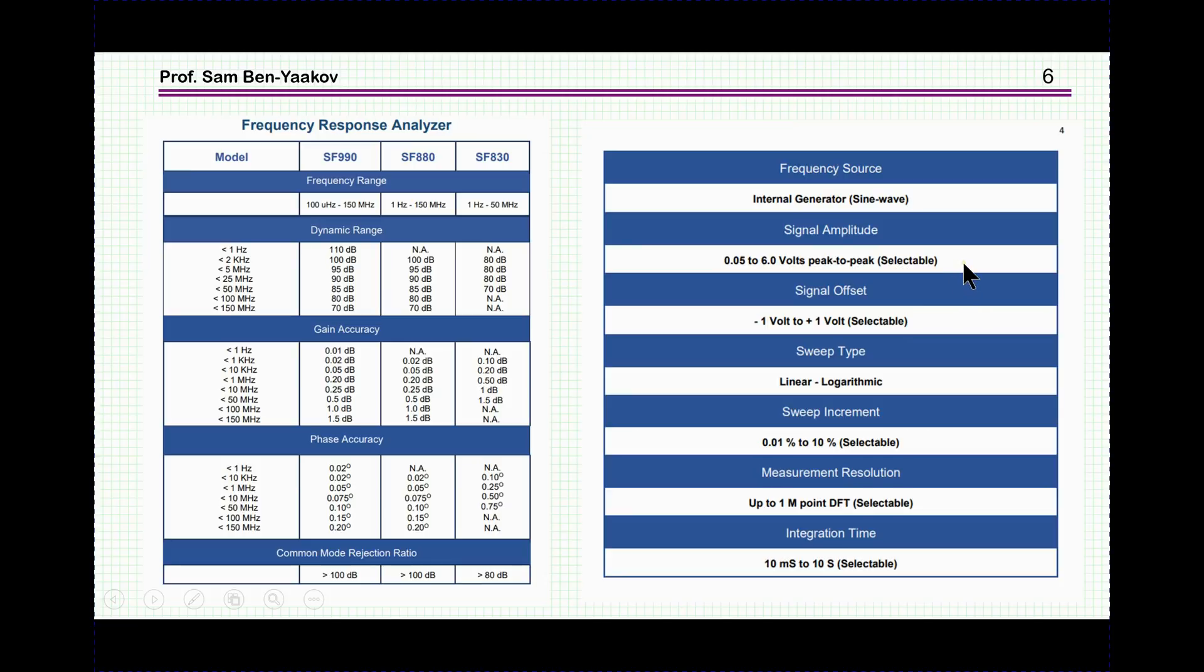So we have a frequency source, the internal generator is the sine wave generator. The amplitude is 0.05 to 6 volts, so it can be selected. It doesn't say what's the output impedance. I hope it is 50 ohms. The signal has an offset that's not that important. Sweep could be linear or logarithmic. The sweep increment could be by percent. And then you can actually choose the frequencies, the specific discrete frequencies that it will measure at. So there are many options here. And then the resolution of the measurement is up to 1 megapoint of this digital discrete Fourier transformation, which is the algorithm used to extract digitally the information from the signal. And this is very important. Of course, what is important is the bottom line, how well does it do the job. And then it has an integration time between 10 milliseconds to 10 seconds. This is again noise attenuation. Of course with 10 seconds then it will take you forever probably to end the sweep.